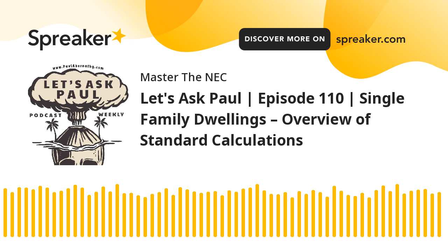So the beautiful thing about this now is that you get to apply a demand factor. Because of diversity that's involved, there are some demand factors that you're going to be able to apply to this. And so that means you need to look at 220.42. Now, the reason that we're jumping out of part 2 and up into part 3 is because now we're going to start adding the pieces for our standard calculation. And that falls under part 3.